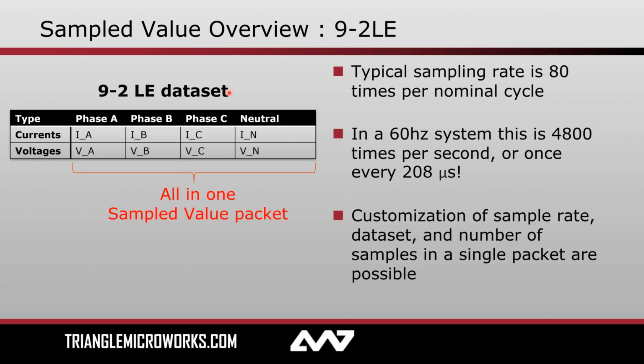When sample values first came out, my understanding is that it was a little bit of the Wild West. So they pared it down into a profile to make it a little bit simpler. That is called 9.2 LE, LE standing for light edition. It defined a smaller subset, an easier way to use it. It defined that we would always have 4 currents and 4 voltages, and that our sampling rate would commonly be 80 times per nominal cycle. Again, this comes out to 4,800 samples per second in a 60 hertz system, or 4,000 in a 50 hertz, every 208 or 250 microseconds, depending on your frequency.